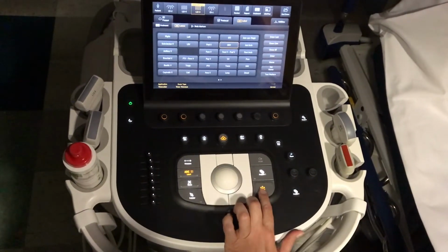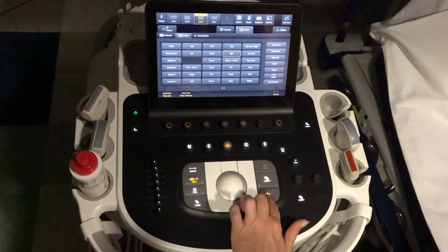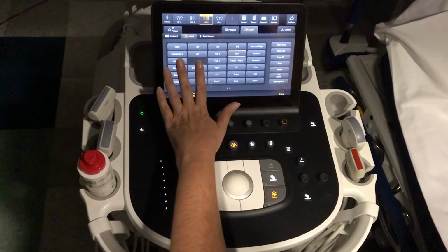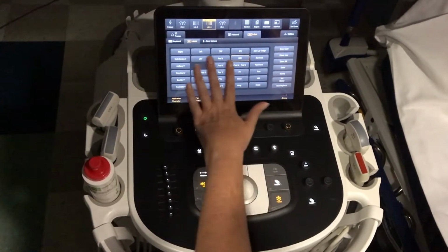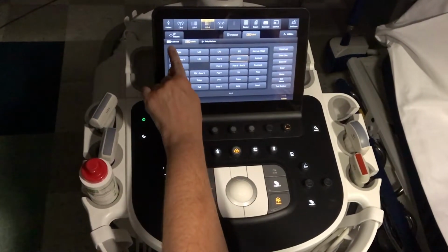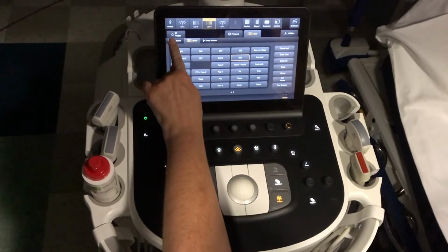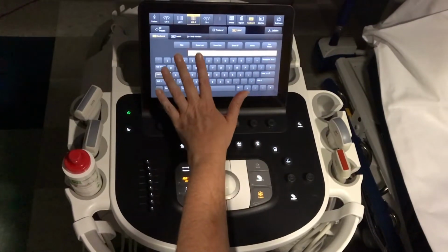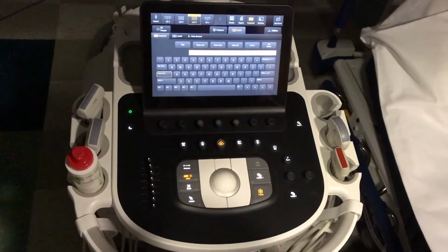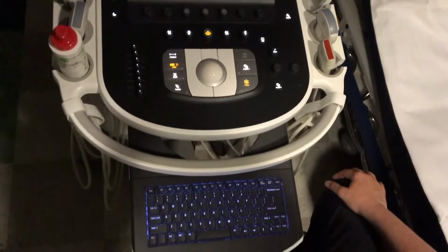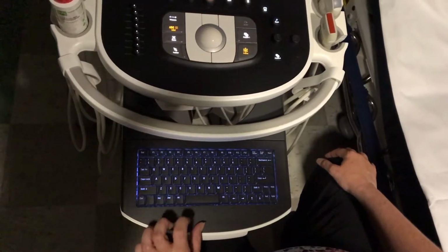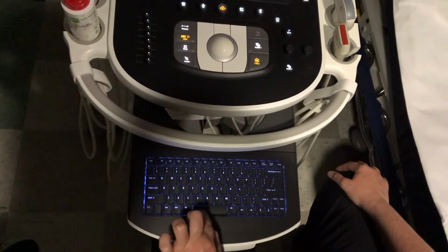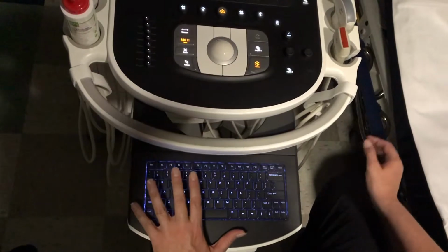Once you have the image that you would like to store, you hit freeze, and you can either use the automated annotation or choose this selection, the keyboard, and then a keyboard will appear on your touch screen.